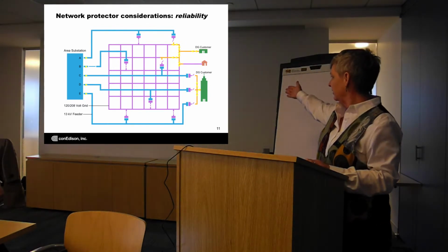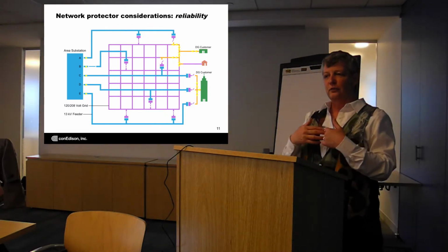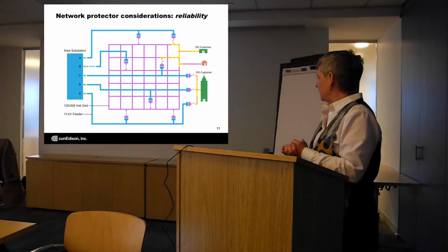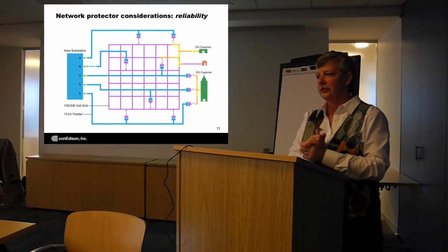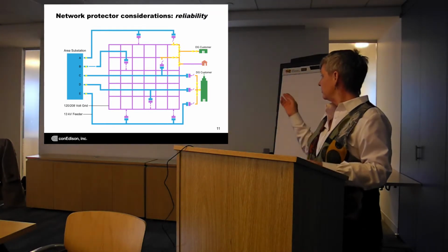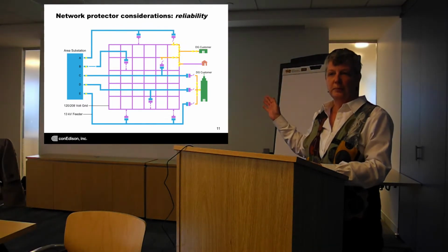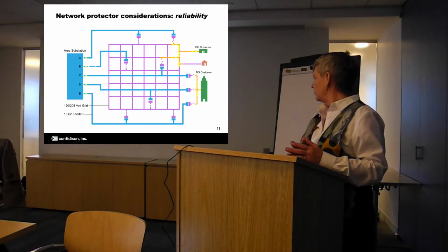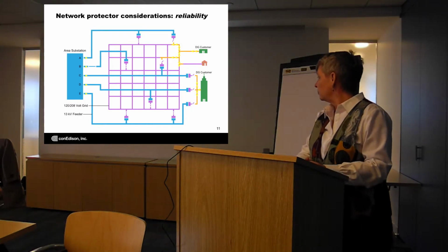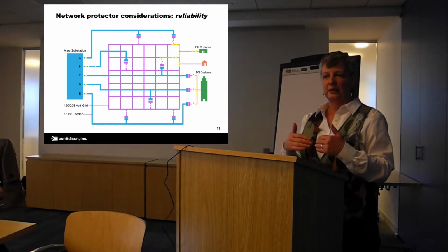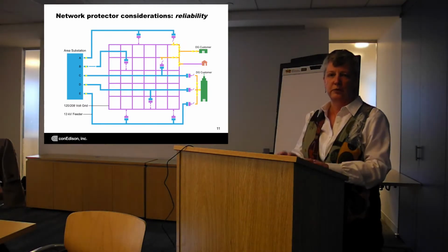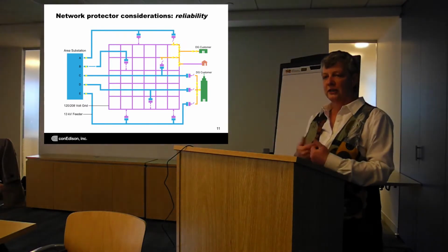And in the case of the large building over here on the right, if you open the network protectors, you've interrupted the supply from Con Edison to that building. So that's something our engineers have to figure out a way to manage around, or the generation that's being installed there has to make sure that doesn't happen. There are fairly basic technologies that can deal with making sure those don't open. And what we're beginning to see is technologies that will actually allow some amount of export through those network protectors, with the ability to operate them from the control room. But these are the challenges that we see.